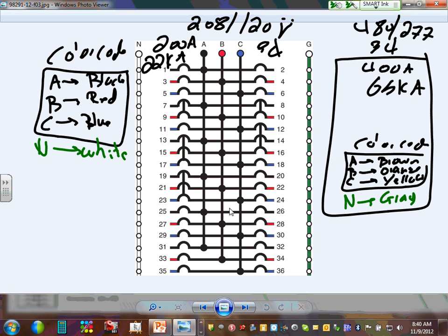If you have 2 panels with different voltages, you have to put the color code of the wiring system for the branch circuits and the feeders. Can I have thumbs up? That's the most misunderstood concept. In the building that we have, do we have 2 voltages? We only have 208, 120. By the way, 208, 120 is 1 voltage system. When I say 2 voltages, I mean 3-phase voltages, like 480, 208. We have only 1 voltage. Do I need to color code on the panels? Very good idea, but I don't need to.